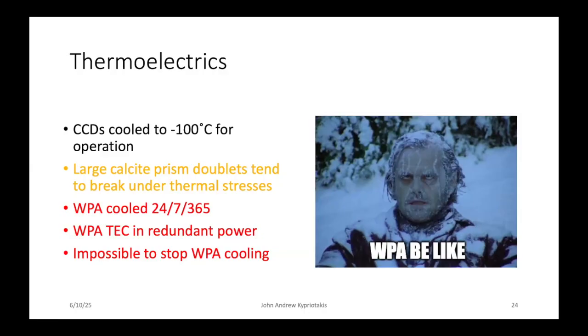And that's because we have them on redundant power. So three power supplies. If one of them fails, we get the first alarm and we get to replace it. If another one fails, we get another alarm and we get to replace that one as well. For all three of them to be broken, someone must have made it on purpose. It's not going to be me, but it's going to be someone. And at least two of those redundant power supplies are off the grid, so we're not going to have a spike from the grid that will fry them. I don't know if I answered the question. The answer is, it's not going to happen.